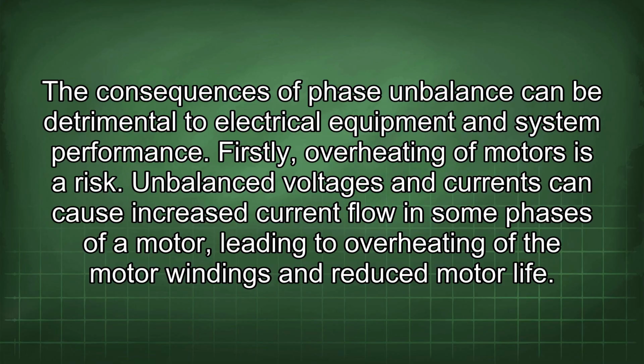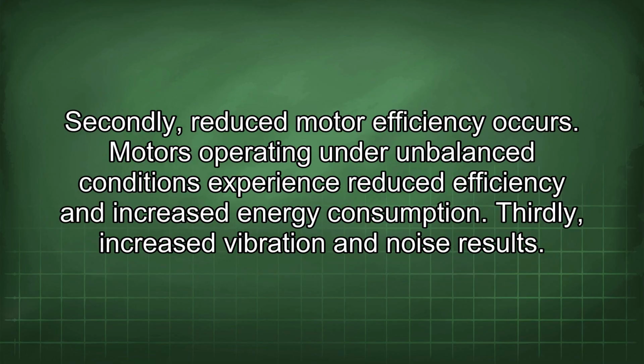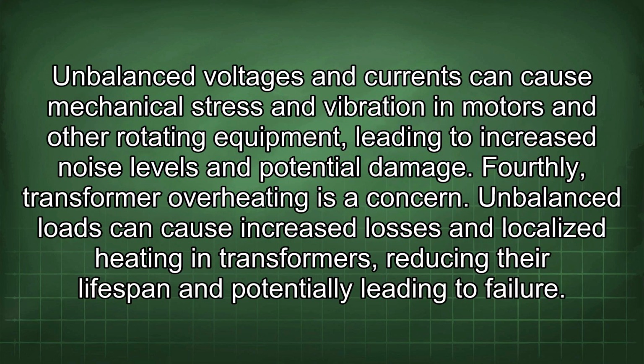The consequences of phase imbalance can be detrimental to electrical equipment and system performance. Firstly, overheating of motors is a risk. Unbalanced voltages and currents can cause increased current flow in some phases of a motor, leading to overheating of the motor windings and reduced motor life. Secondly, reduced motor efficiency occurs. Motors operating under unbalanced conditions experience reduced efficiency and increased energy consumption. Thirdly, increased vibration and noise results. Unbalanced voltages and currents can cause mechanical stress and vibration in motors and other rotating equipment, leading to increased noise levels and potential damage.